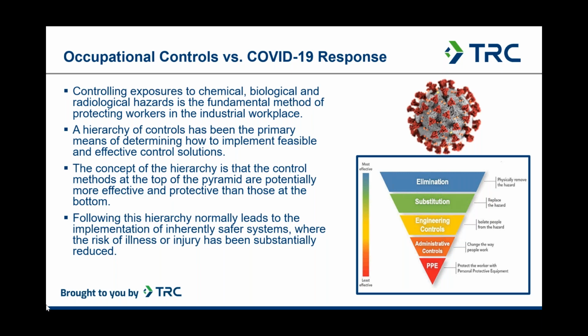With regard to ventilation, one must consider the pathways or modes of transmission for a virus that Dave mentioned, and these include direct contact, indirect or surface contact, inhalation, and fourth, the airborne transmission pathway, or what we often refer to as the long-distance transmission pathway. Thus far, the evidence points to contact and inhalation as being the primary pathways of transmission, but that does not mean that we should rule out or do nothing with the ventilation systems in the spaces that we occupy. In fact, in most buildings, the ventilation systems are typically out of sight, out of mind until they don't work. Next slide, please, Dave.